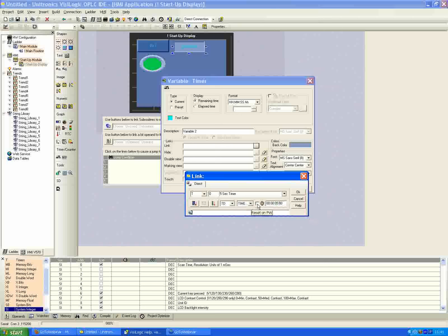It's a good idea to have the reset on power-up checked whenever you do a download and reset, so you don't have a previous value stuck in the timer that causes confusion about why the timer isn't counting down. As a general rule of thumb, have this checkbox selected for most programs. Obviously there are situations where you don't want that, but it's a good general practice.